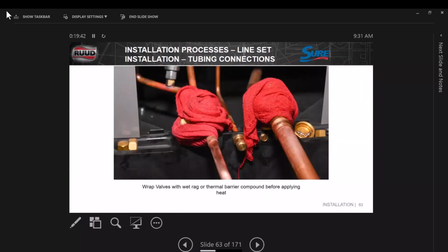We want to use some type of rag. This is a bad example because we want some kind of cotton rag that's going to hold the moisture in, like a terry towel or something. There's a good rag here, wrap it, or any kind of thermal paste. If you have a favorite thermal paste and you know it works well, use it. We've got to keep these valves cool. If we don't, we end up with warped threads in there, and they're hard to get open, hard to get closed, or the seals melt. So we've got to keep them good and cool.